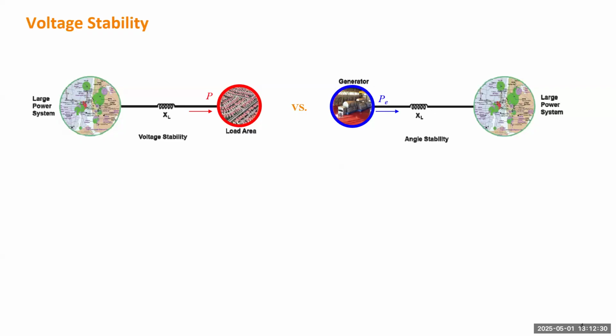We showed this picture before in the first session when we quickly went through all the stability problems. This picture is a very good example to give you ideas on the differences between voltage stability and angle stability, or rotor angle stability. Angle stability may include both small signal stability and transient stability, depending on which model you are using. Angle stability usually happens on some single small generator connected to the large system. So you can utilize a single machine infinite bus system to model this, and based on the power angle curve, we can use the equal area criterion to study the angle stability. Voltage stability happens with a load area connected to a large system through a long transmission, and there's not much local generation to support the load. You have to utilize the tie line flow from the remote area.